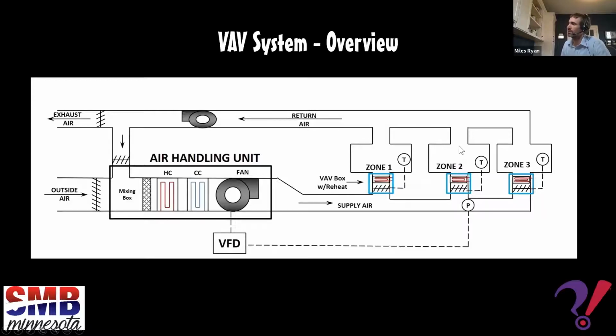Now, zone 2, also served by the same system, might be calling for heating. Maybe the space temperature is falling below space temperature heating set point, in which case the first step would be to start reducing the amount of cool air that's being sent into the space. Now, I will say that there's different ways to control VAV boxes, but I'm detailing here the most conventional way. That most conventional way, if we're overcooling a space, would be to reduce the airflow going into the space, so reduce the airflow set point for that VAV box. You can't completely go to 0 though, because occupants in that space are going to need some ventilation air circulating through that space. So we might go to some minimum airflow set point.